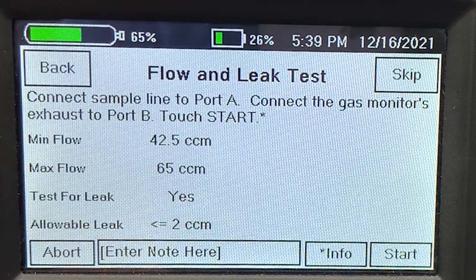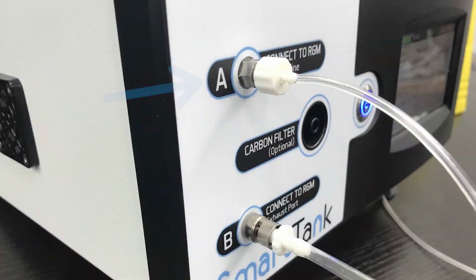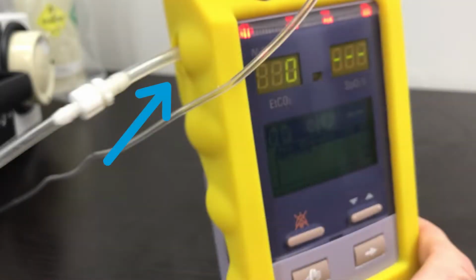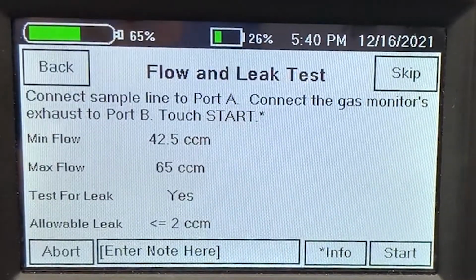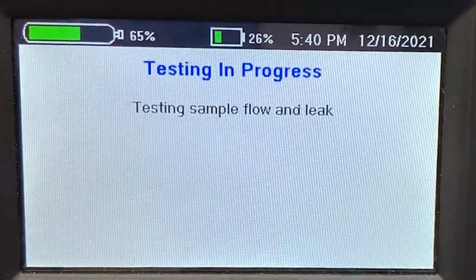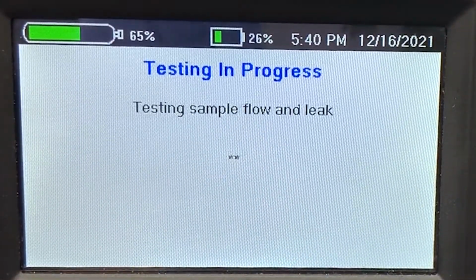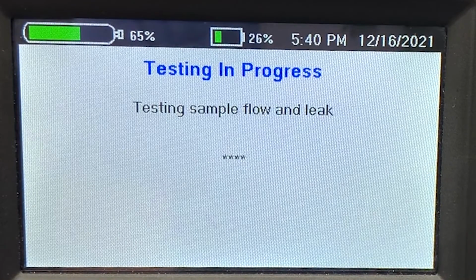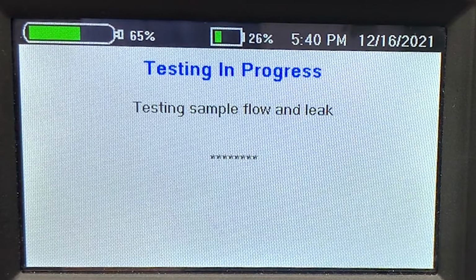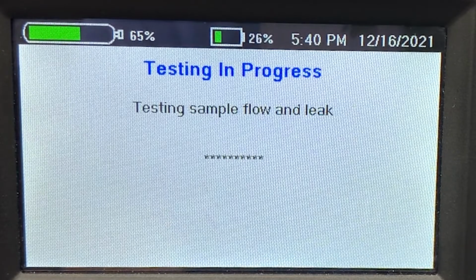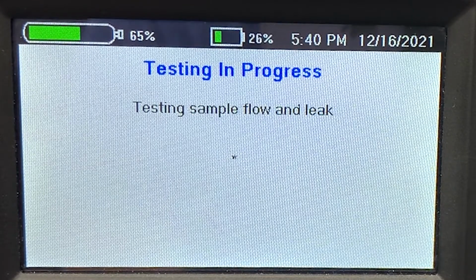So the next test is the flow and leak test. We already have the sample line connected to port A on the smart tank. We now need to connect port B of the smart tank to the exhaust of the monitor. The smart tank will measure the sample flow rate, and then it will also measure if there are any leaks inside the monitor.